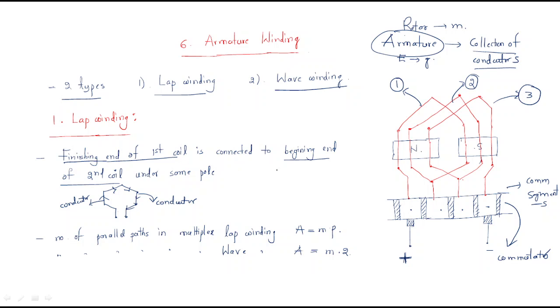The finishing end of the first coil is connected to the beginning end of the second coil under the same pole (north pole). The finishing end of the second coil is connected to the beginning end of the third coil. When the arrangement is like this, we call it lap winding. One conductor is in one pole and another conductor is in the other pole for each coil.